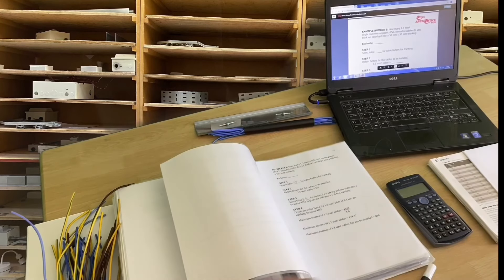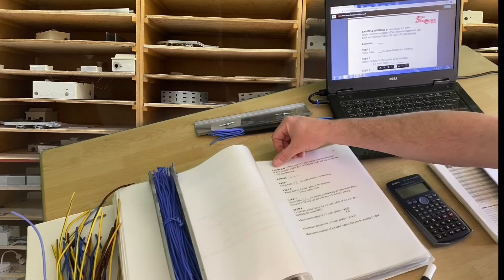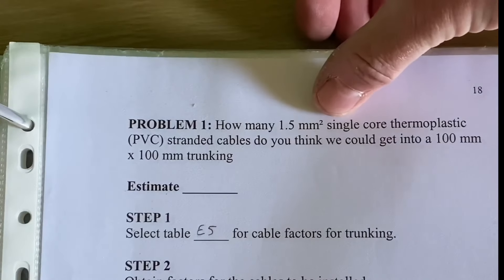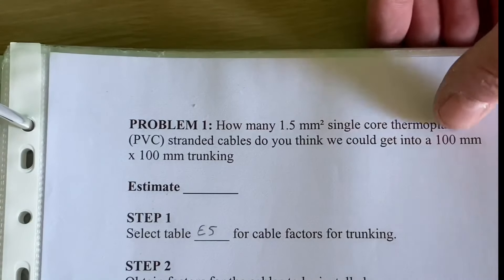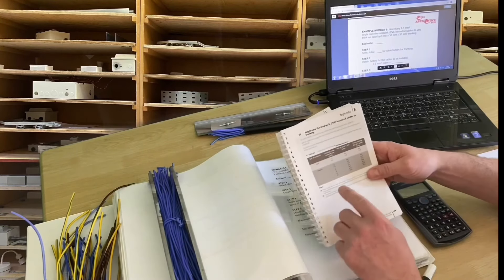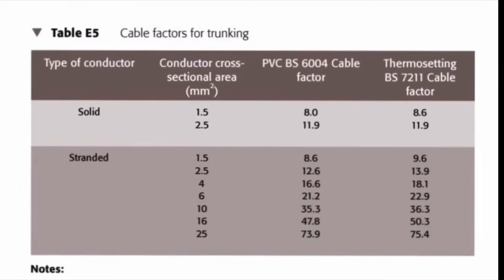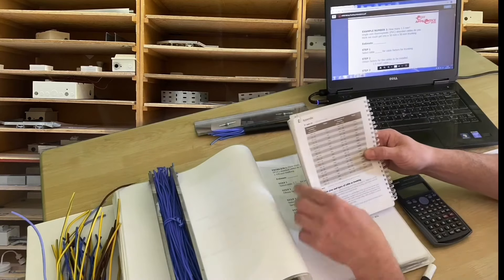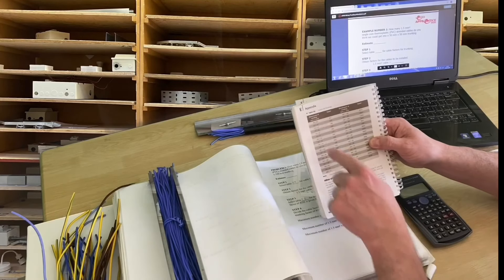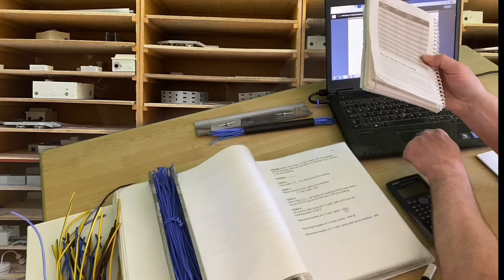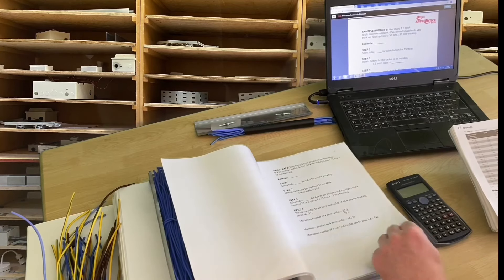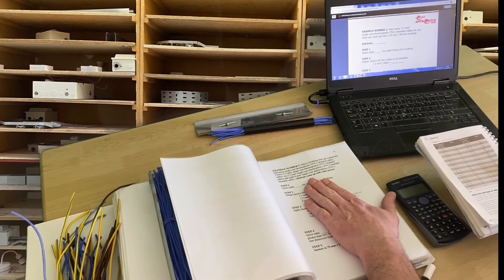The next page is a problem for you to work through yourself. Problem one: how many 1.5mm² single core thermoplastic stranded cables can fit in a 100 by 100mm trunking? You use the same cable factor from E5 — 8.6 — but look up the different trunking factor in E6 for 100 by 100. Problem two involves 4mm² cable in 75 by 75 trunking. Work through those, then we continue to example number two.